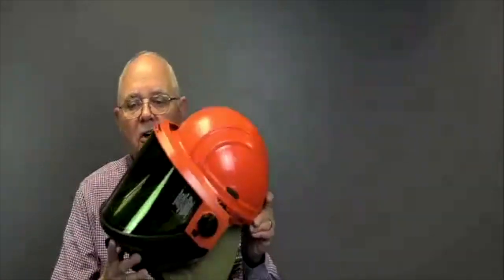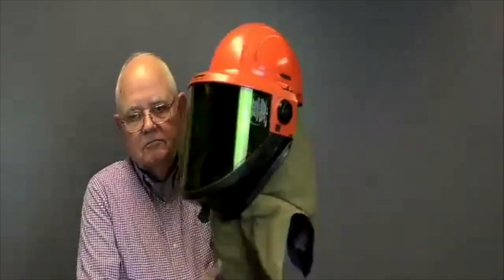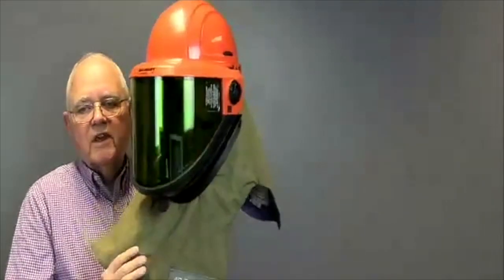If you're using the table method, in other words, if you have not yet done an incident energy analysis on your facility, you're going to have to use the category method, the table method. For all of our medium voltage equipment, with the exception of arc-rated switchgear, which would not require any PPE if the doors are latched and secured to rack a breaker in or out, if you're going to do any other type of medium voltage work, the table method ends up being PPE category 4. For PPE category 4, we have to wear arc-rated clothing rated for a minimum of 40 calories. So we end up with a hood, something like this, where the face shield is rated for 40 calories, and of course all of the garment material is rated for 40 calories as well.